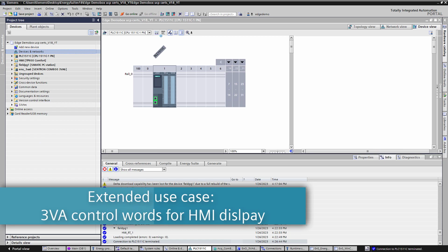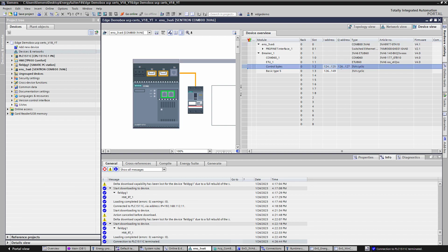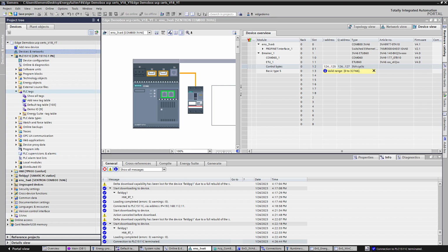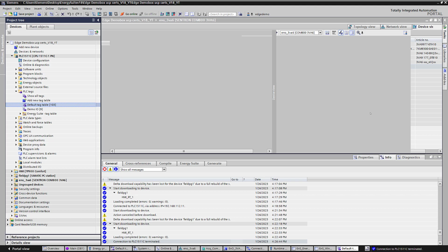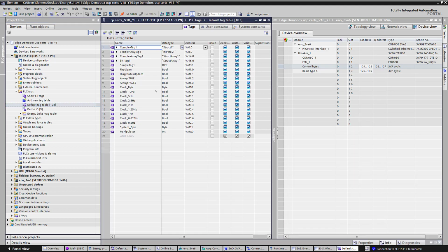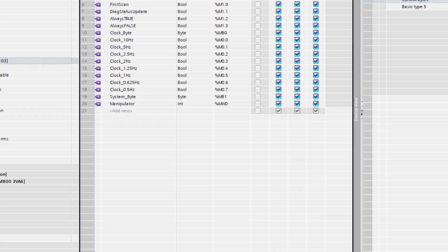The remainder of this demo are extended topics that are outside the scope of Energy Suite. I also feel like I wouldn't be demonstrating much if we didn't talk a little bit about the control bytes that are available from the device, being that it's an I/O device. We can pull in the I and Q addressing that you see here. Using the default tag table, we'll go ahead and declare some control and status words for the 3VA6 breaker. These tags could be used throughout programming situationally. For example, in the HMI, these tags could be used to provide feedback about the breaker visually.